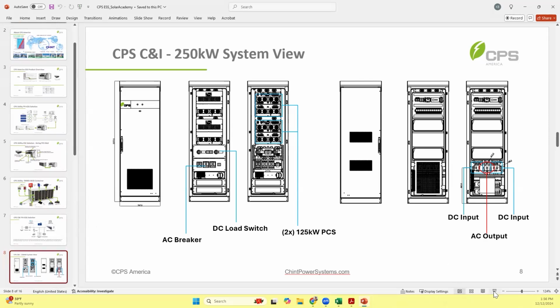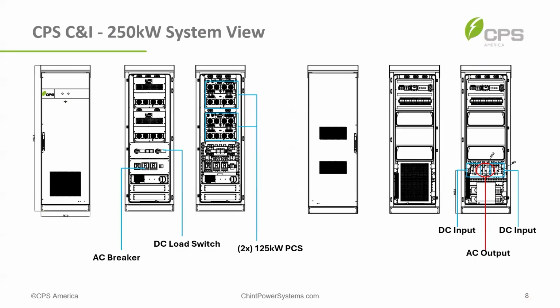So just to put it out simply, what we're looking at here is the front side of the PCS cabinet. In the PCS cabinet, denoted right there, there are two 125 kW PCSs, and each one controls its own battery cabinet. For the 125, when there's only one of those 125 PCSs, you only have one cabinet, so you don't really get the benefits of the string design, just because it's so small.